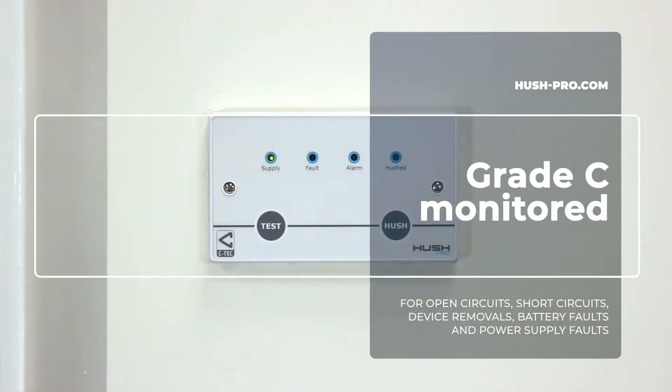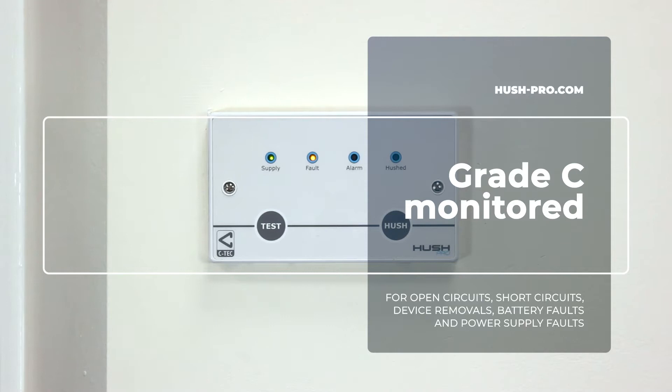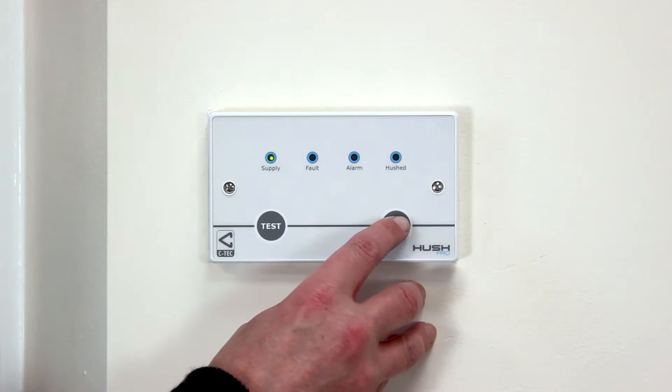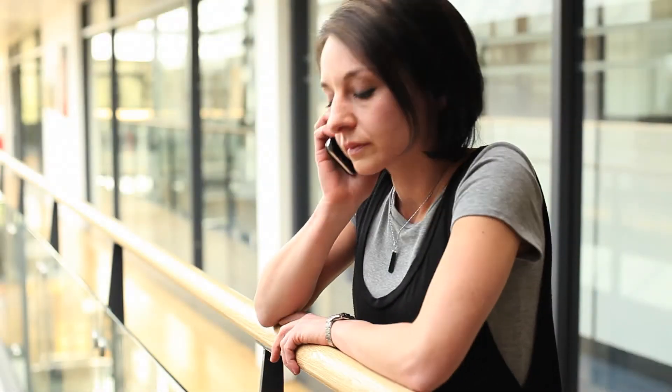Such a fault is brought to the attention of the occupant by a buzzer sounding. The occupant can then come along and press Hush to silence the fault for 24 hours. The idea being they contact their landlord and ask them to fix the fault.